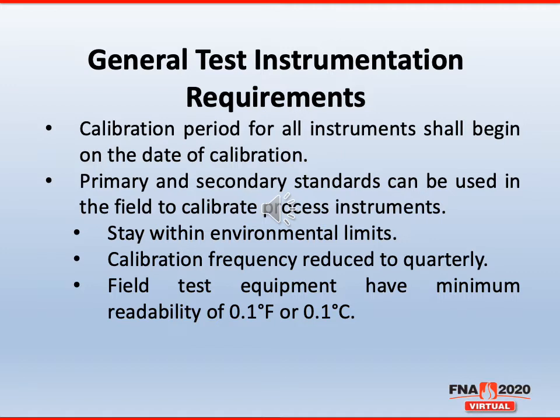We also addressed that primary and secondary standard instruments can now be used in the field to calibrate your process instruments. We do have a couple caveats on that: they must stay within the environmental limits described by your manufacturer's tolerances. So if your manufacturer's tolerance for a standard instrument says as long as it stays within 105 degrees Fahrenheit and less than 90% humidity, and your shop is in that realm, yes, you can go out and use your standards to calibrate your process instruments.